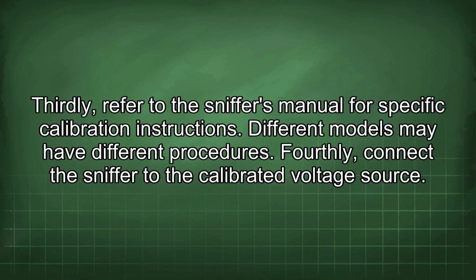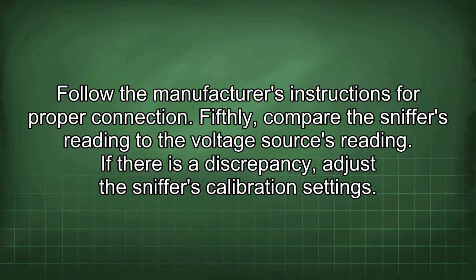Thirdly, refer to the sniffer's manual for specific calibration instructions. Different models may have different procedures. Fourthly, connect the sniffer to the calibrated voltage source. Follow the manufacturer's instructions for proper connection. Fifthly, compare the sniffer's reading to the voltage source's reading. If there is a discrepancy, adjust the sniffer's calibration settings.